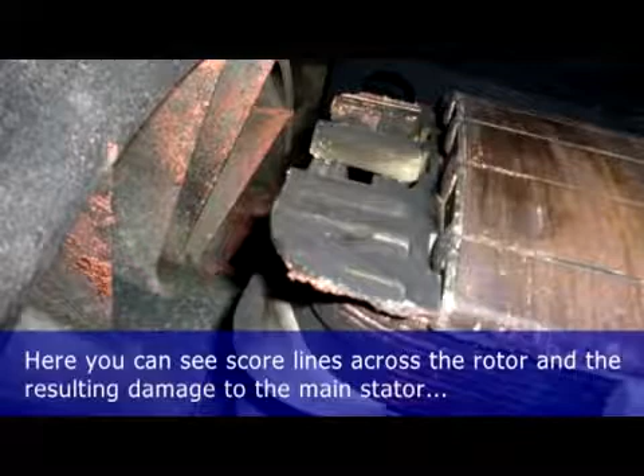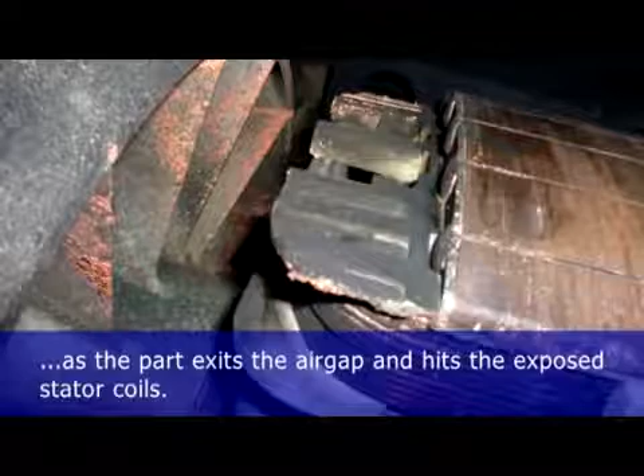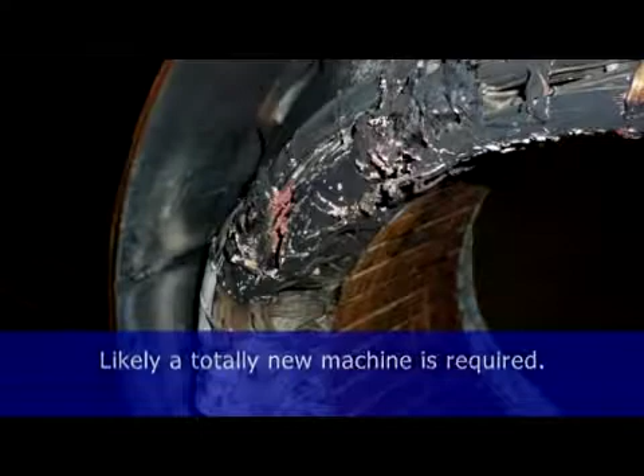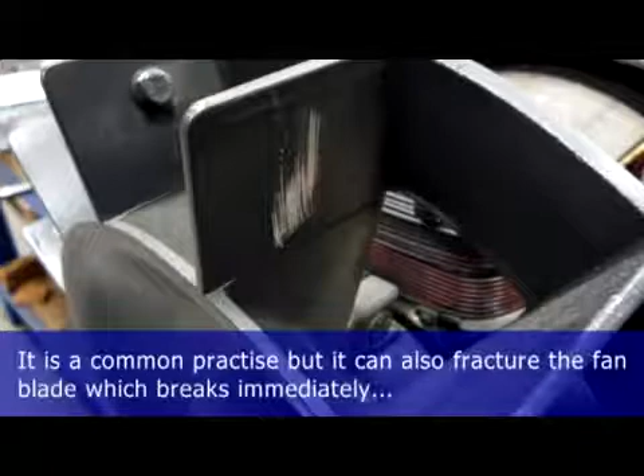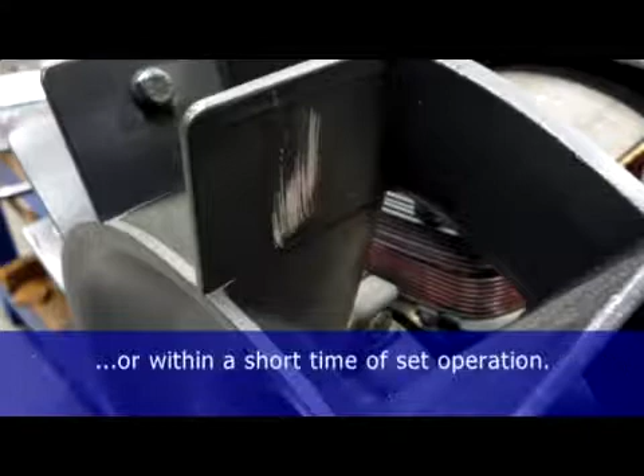Here you can see score lines across the rotor and the resulting damage to the main stator as the foreign part exits the air gap and hits the exposed stator coils. Likely a totally new machine is required. Always try to avoid barring the genset using the alternator fan. It is a common practice, but it can also fracture the fan blade, which breaks immediately or within a short time of set operation. The resulting damage is the same and a new alternator is required, but on an invalidated warranty.